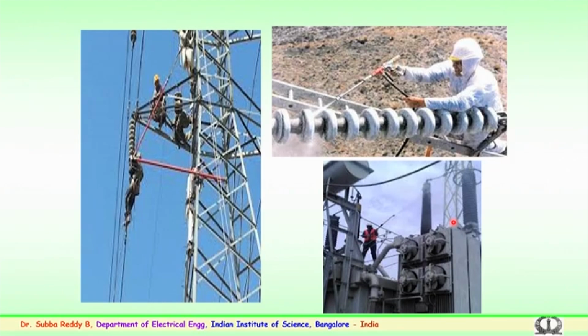Several others, as mentioned, use the dry cleaning method with a plain cloth, or if the hardness is more, the hardness is removed with the help of solvents or liquids which can clear the pollutants on the surface. This cleaning is very important, else, as you can physically see, the deposit builds up over a period of time, the creepage reduces, and flashover of the string happens during monsoon conditions, which is unwanted for power system utilities. So necessary procedures, a plan and regular periodic maintenance are essential. Different methods, either in energized or de-energized conditions, have to be carried out.